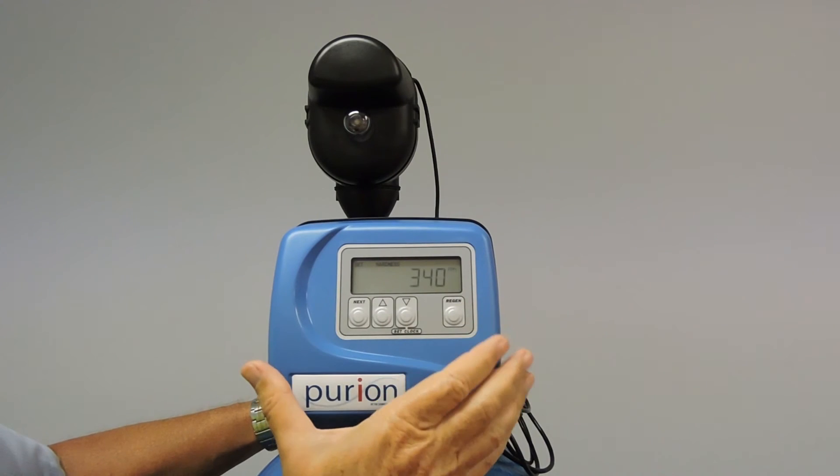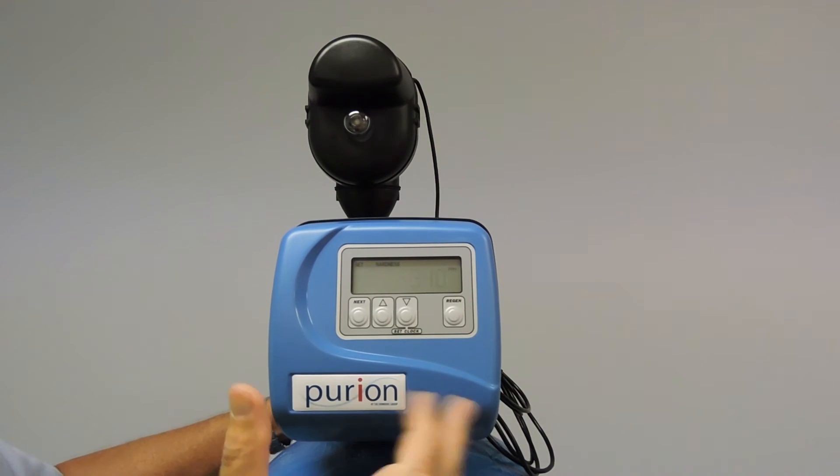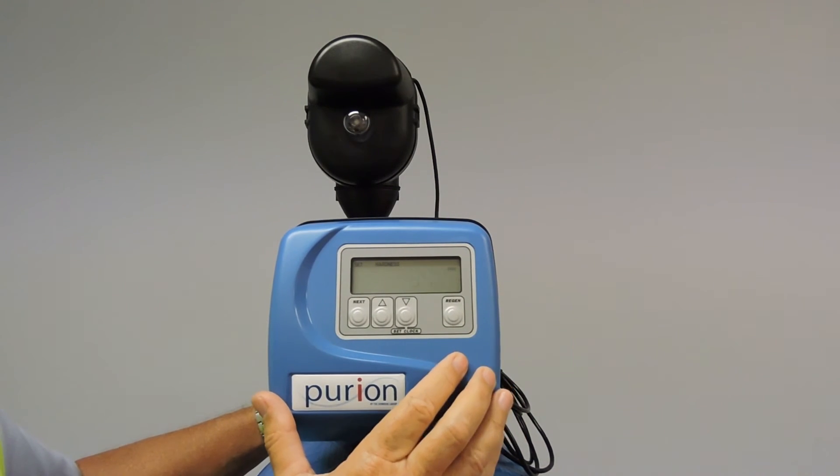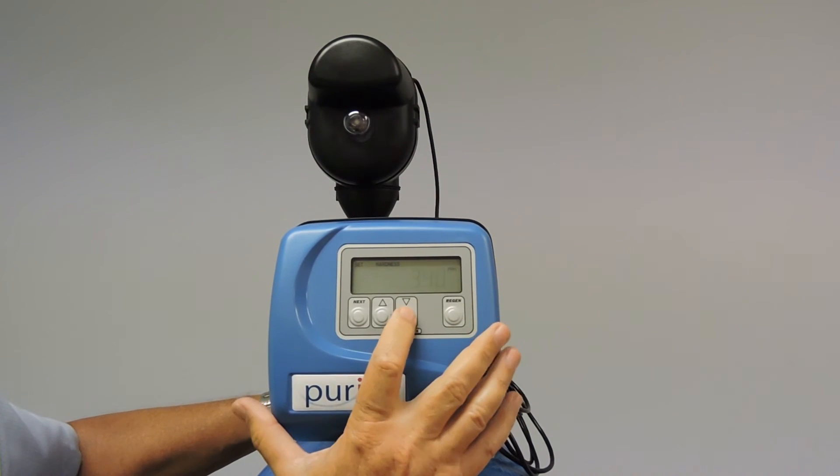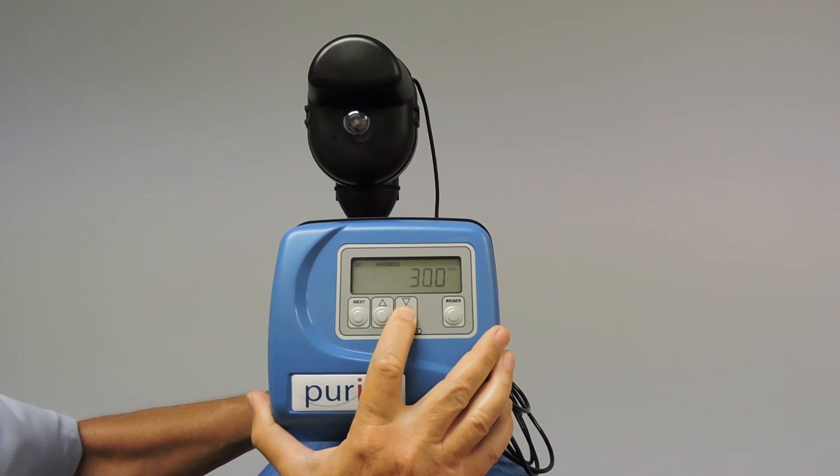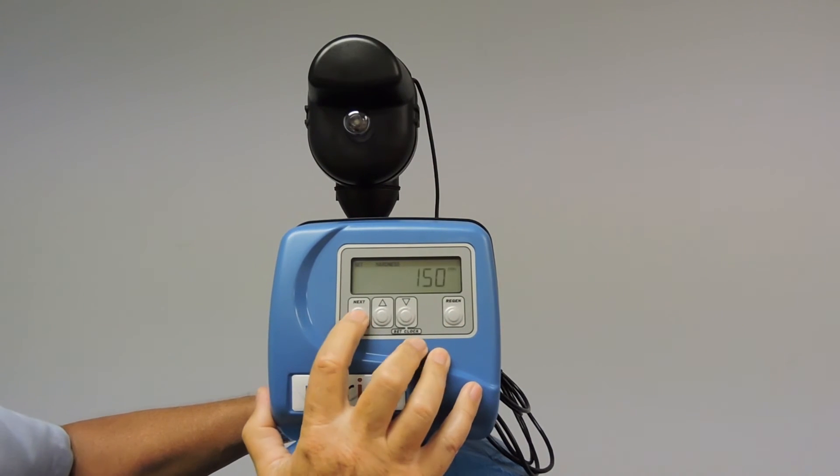The first one is hardness. And this is where we select the water hardness that we are going to be using. In our case we'll just use a generic figure that we use of 150. So I'm going to scroll down to change it to 150 parts per million. And accept it.